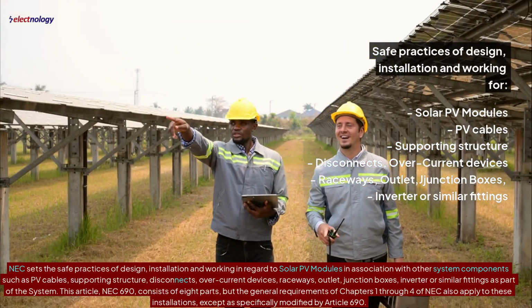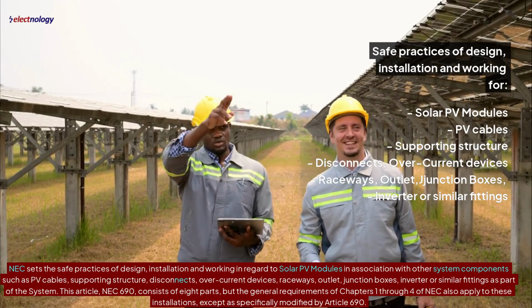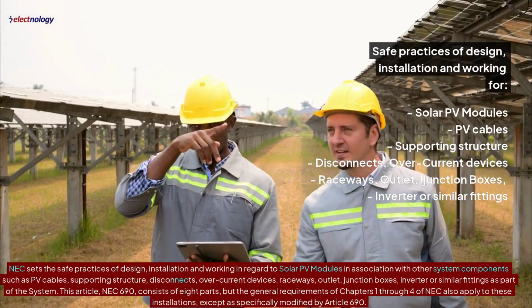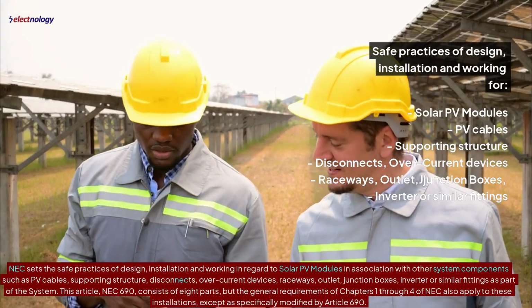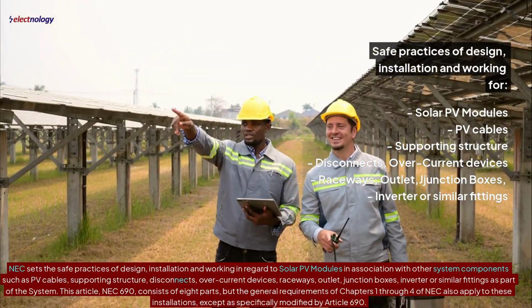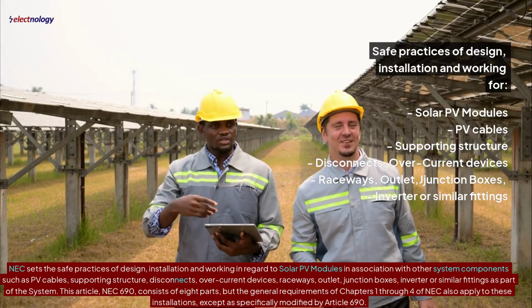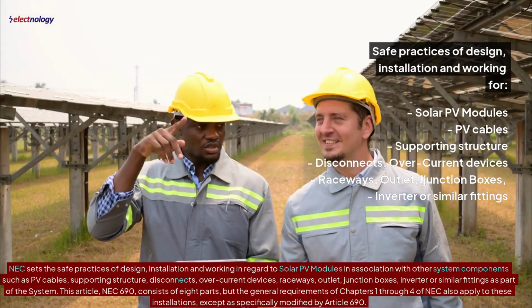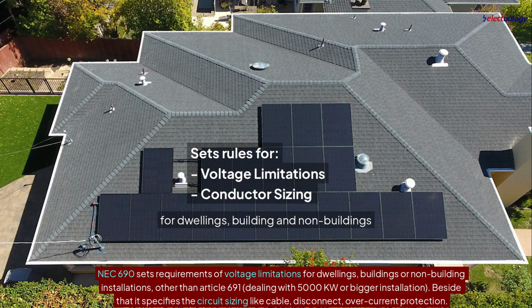This article, NEC 690, consists of 8 parts, but the general requirements of chapters 1 through 4 of NEC also apply to these installations, except as specifically modified by Article 690. NEC 690 sets requirements of voltage limitations for dwellings, buildings or non-building installations, other than Article 691, dealing with 5,000 kilowatts or bigger installation. Beside that, it specifies the circuit sizing like cable, disconnect, overcurrent protection.